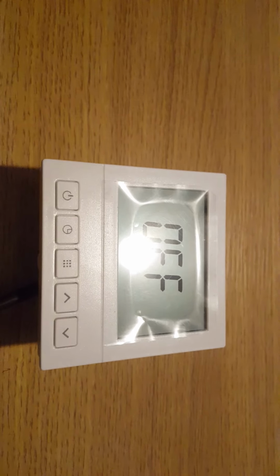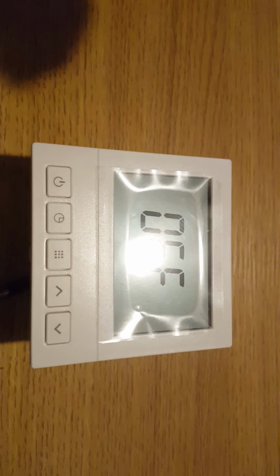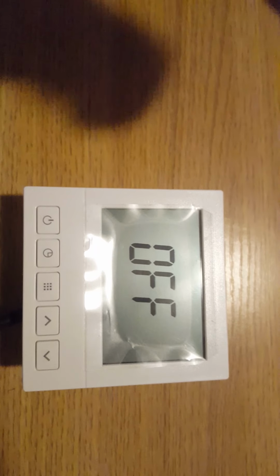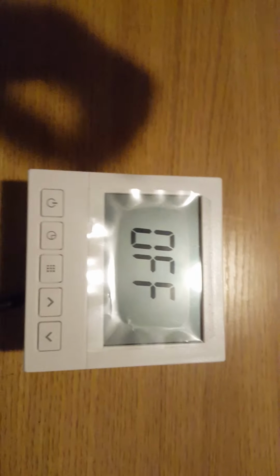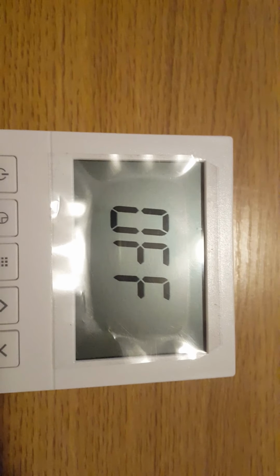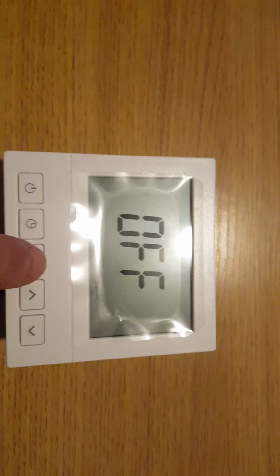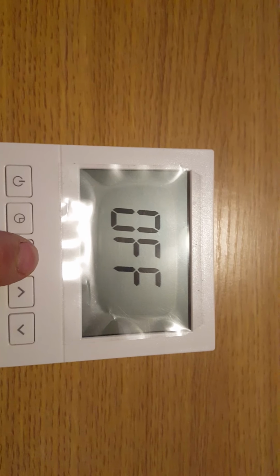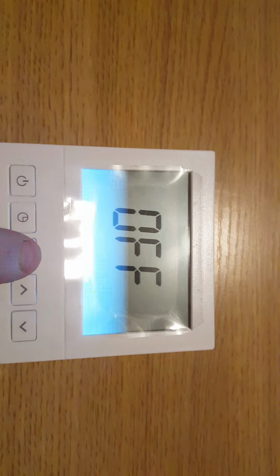Okay, this is a digital programmable thermostat supplied by AM UFH Limited. It's quite a very simple thermostat to program and use. The electrical connections, it does have a switch live and it also has a no volt switch, but that's for the qualified electrician to sort out. Now as for programming it, with the thermostat switched off, if you hold down the program button for 5 seconds, it takes you into the programming mode.